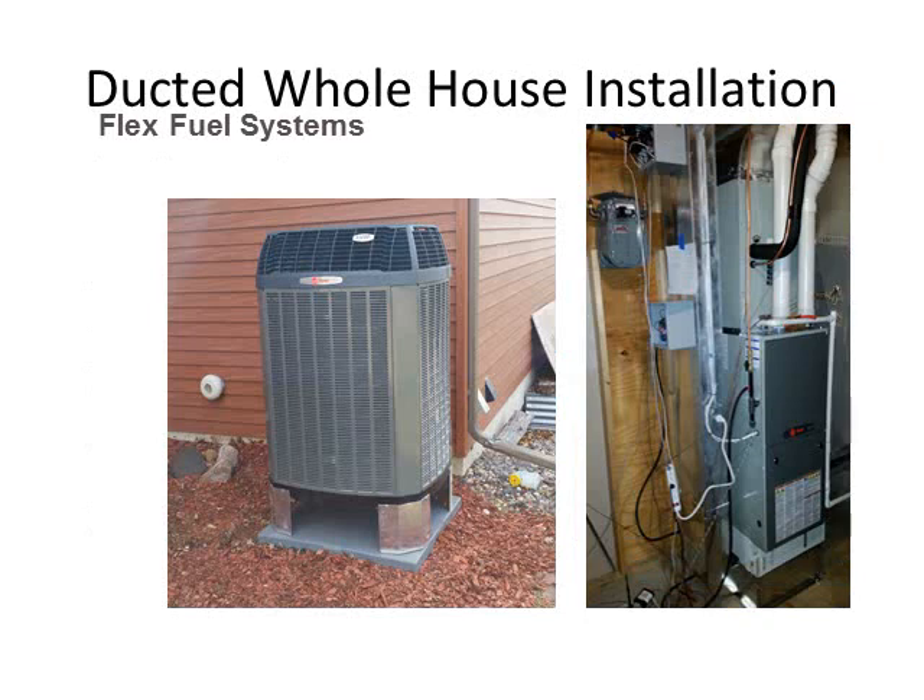Here we have pictures of one of our ducted Flex Fuel Systems. The picture on the left shows the outdoor unit, which looks very similar to a split air conditioning condensing unit. The picture on the right shows the inside unit, which looks just like a condensing furnace — because the backup system for this heat pump is a condensing propane furnace. You can also see the line set for the refrigerant coming in at the top right, which provides the path for refrigerant to flow through the indoor unit and heat and cool the home.